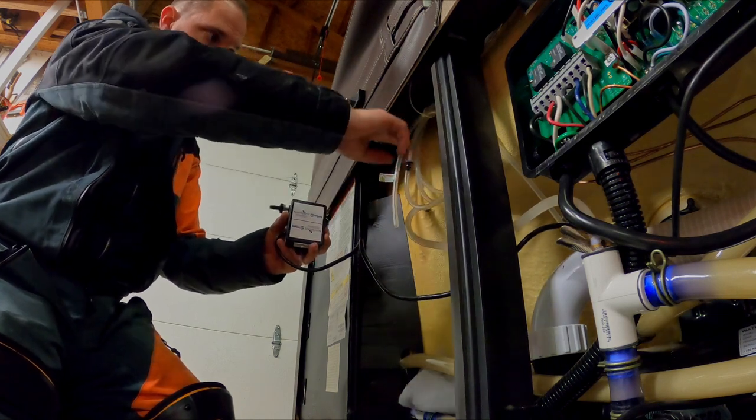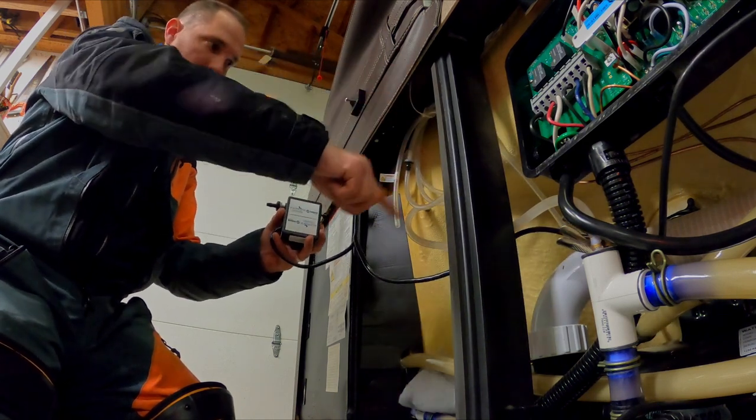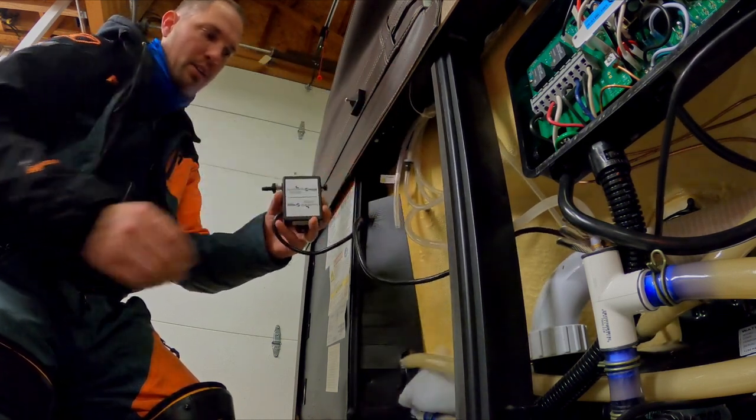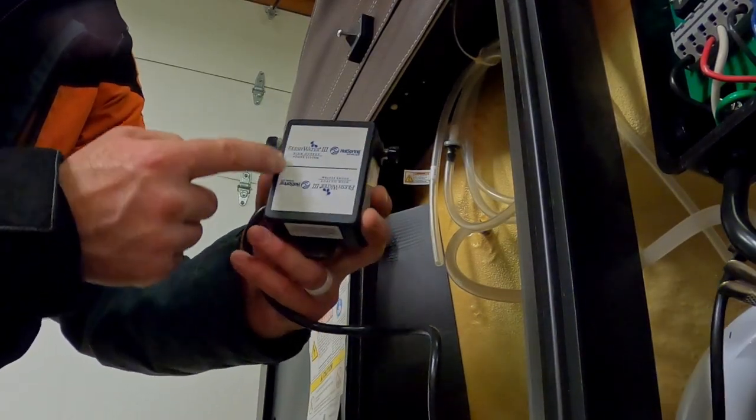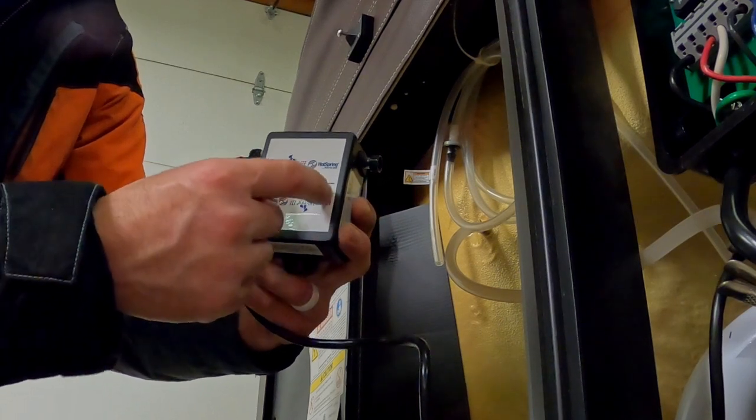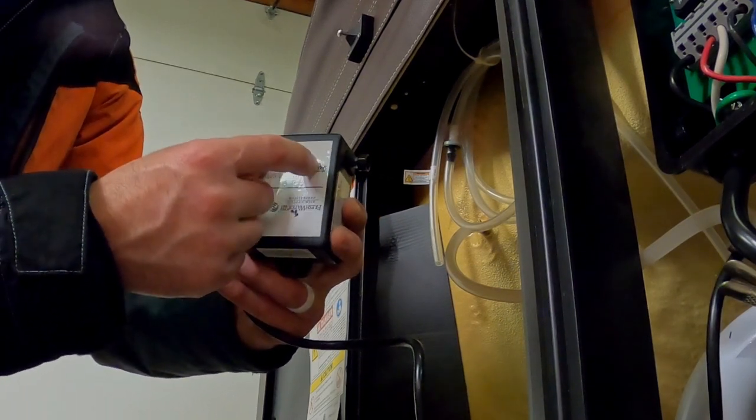I'm going to do that because, like I said, if somehow water gets past this check valve and makes it up over the water line and through the loop-de-loop and makes it back to the ozone generator, if I were to mount it this way, the water would get back through there and it would drip down inside the box.